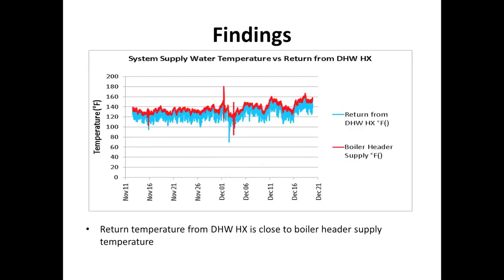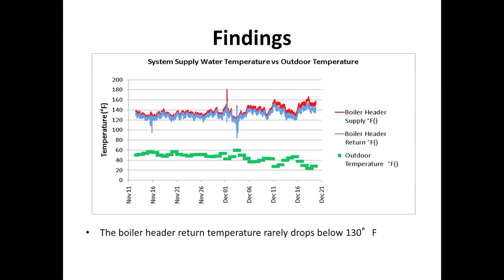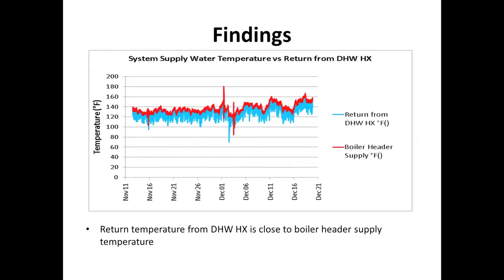So here, looking at the same chart, the previous one just showed the outside temperature and how the building supply temperatures also responded to outside air temperature, verifying the outside temperatures did call for heating. Here we looked at just those conditions themselves, in part load and full load conditions alike. The building supply temperature didn't vary too much.